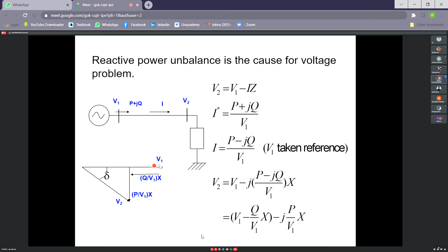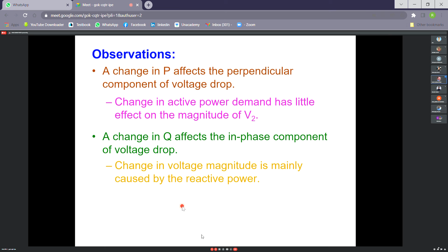What we can infer from this diagram is that P and delta are strongly coupled, and Q and V are strongly coupled. That means the active power flow through the lines can be changed by controlling the voltage phase angles. Reactive power flow can be changed by controlling the voltage magnitudes. So Q and V have a strong coupling. Is it clear till now?